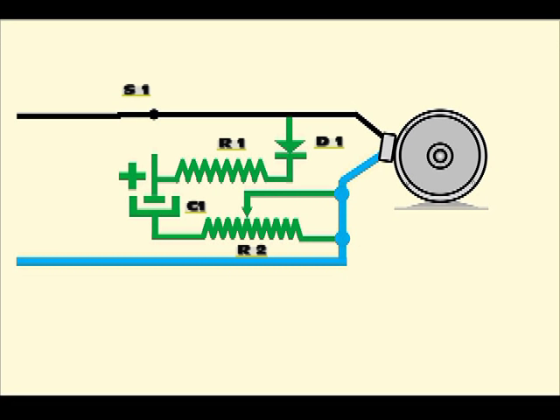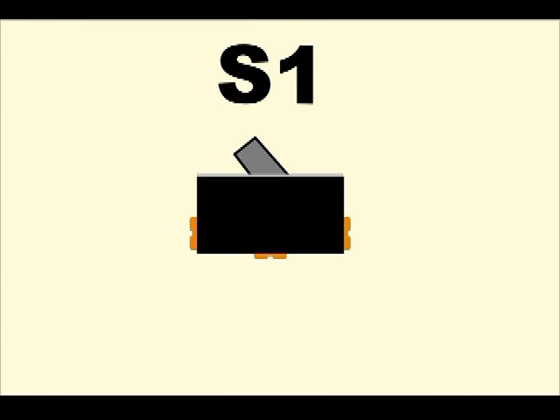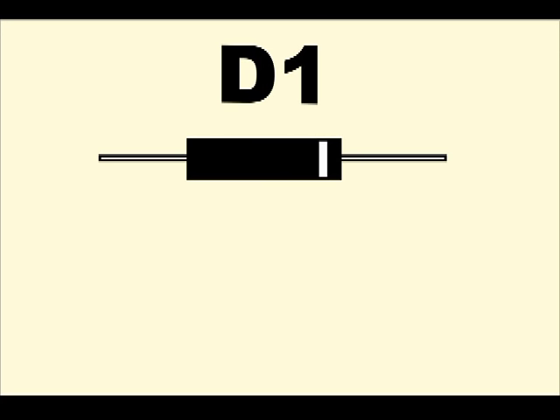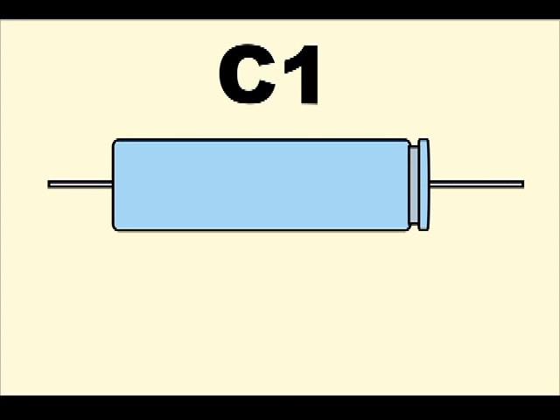In a typical extractor fan circuit, using a one-third horsepower motor operating at 220 volts AC in a single phase, the components could be of the following values. S1: one pole switch, two positions. D1: 1N4007, one amp, at one kilovolt reverse peak. C1: 100 microfarads, 450 volts.